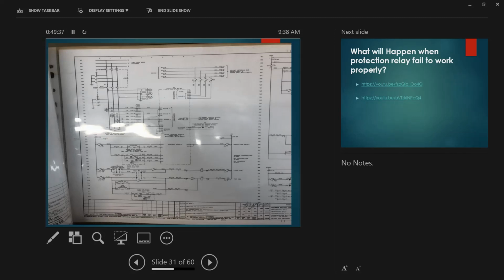Now, we run through all of this safety precaution, so keep in mind the relay should be properly ready for testing by looking at those scenarios. Another one as well is not only looking at the hardwire, because protection nowadays, the relay can also talk through communication, so we can't see that just by looking at the drawing. We need to study the logic, or they call it a small PLC inside the relay. So hardware is different from software. That's also something we always forget, looking at the logic settings of the relay.